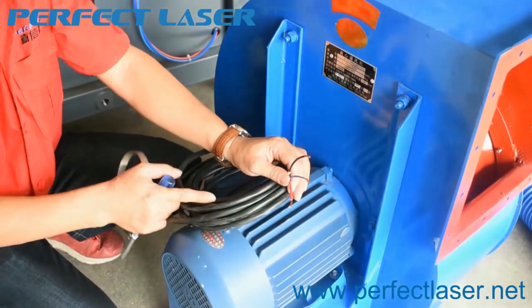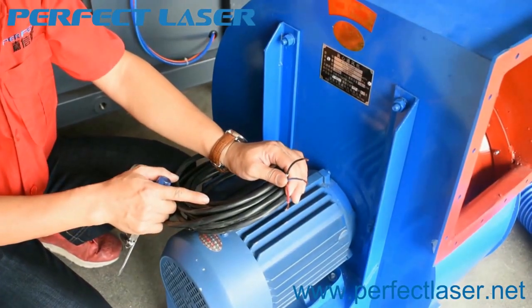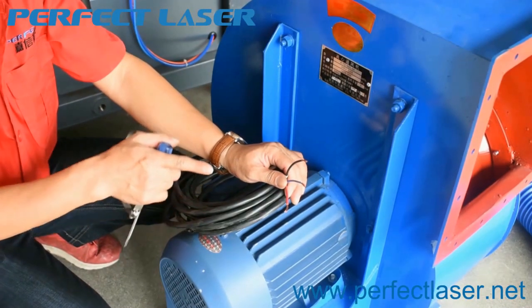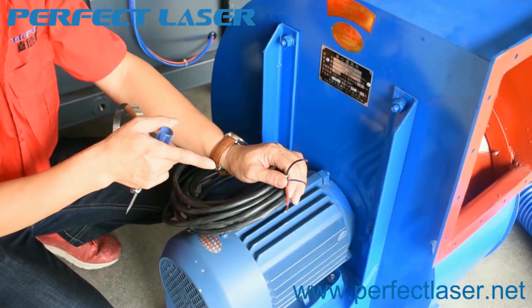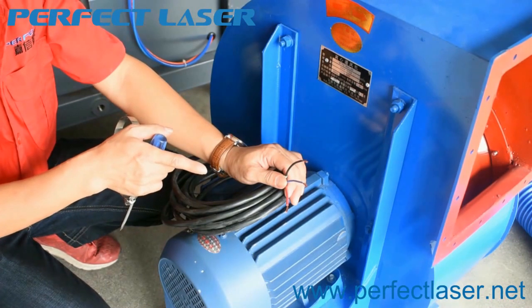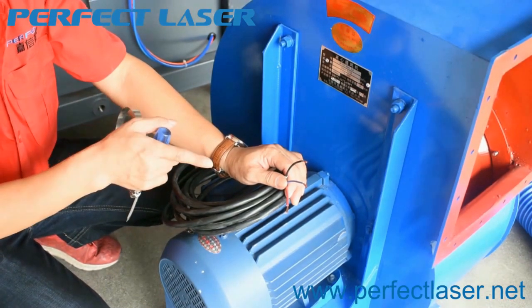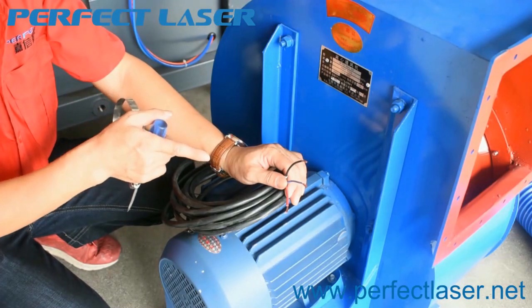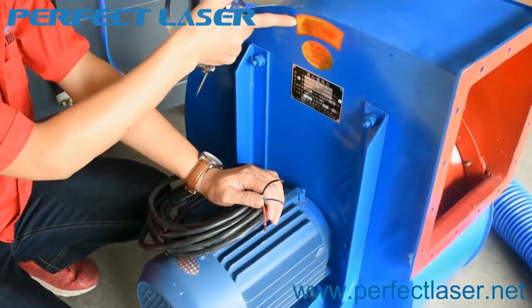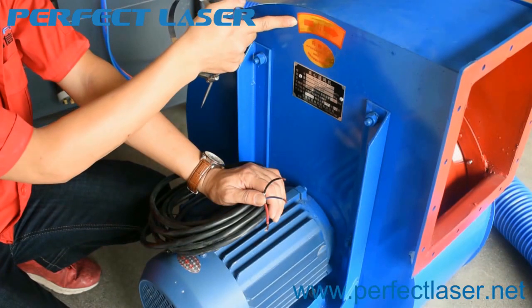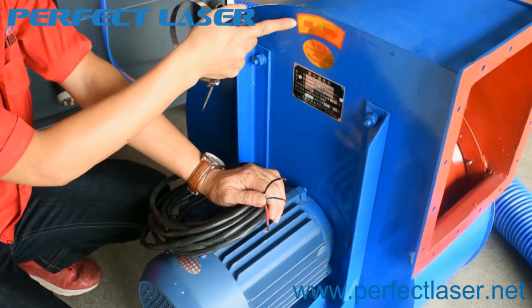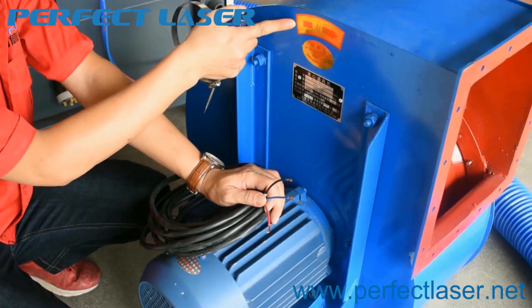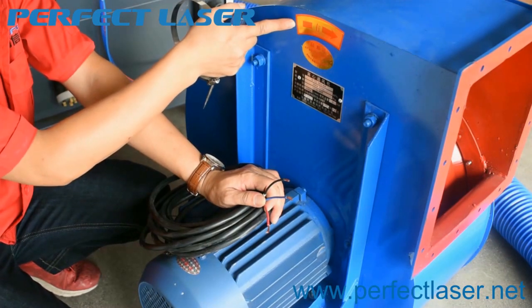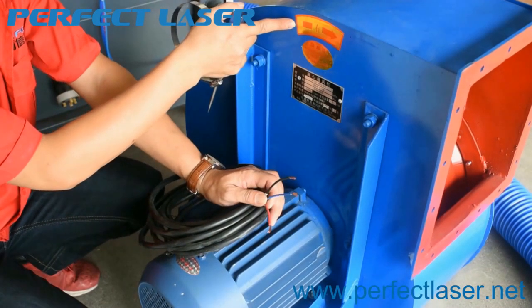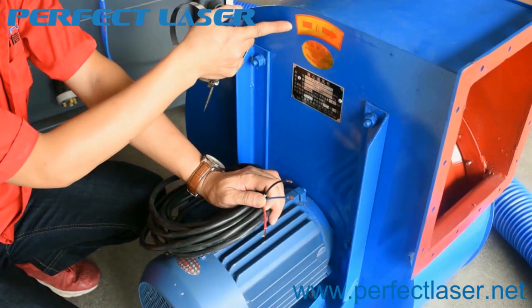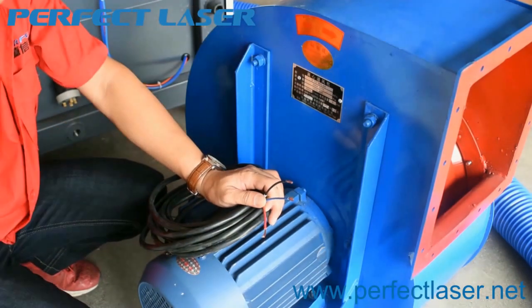This is the main power cable for the exhaust fan. Please connect it to the 380 volt 3-phase power. When you have connected the wire well, turn on the fan and check its direction of rotation. The fan should turn right. That would be okay.